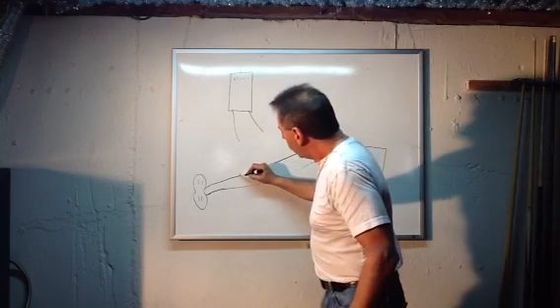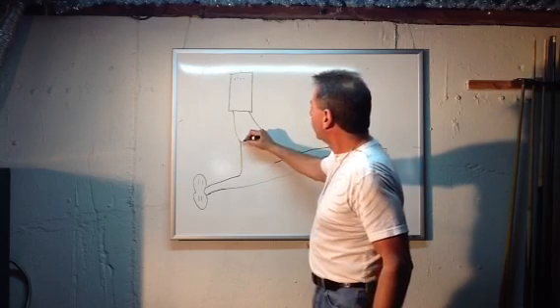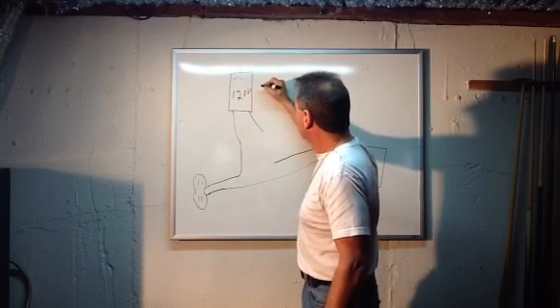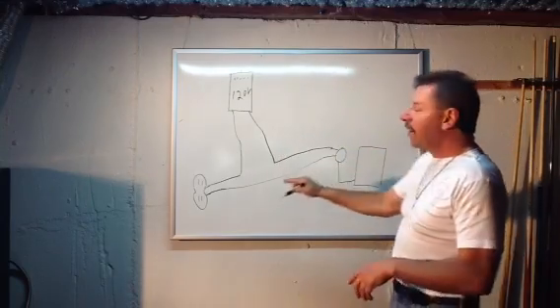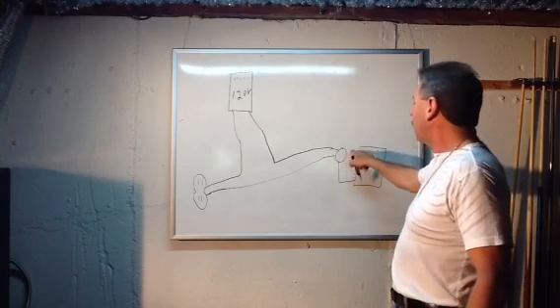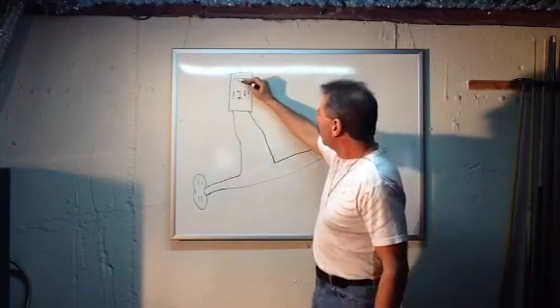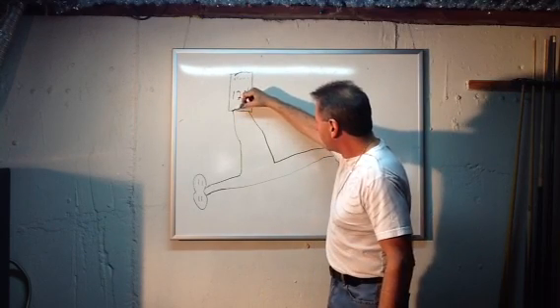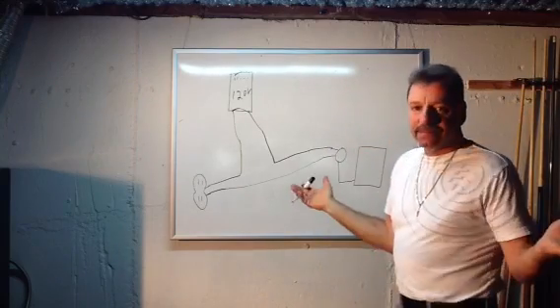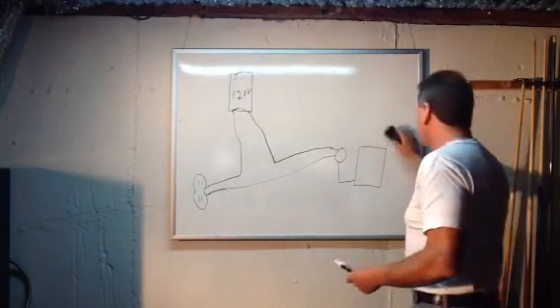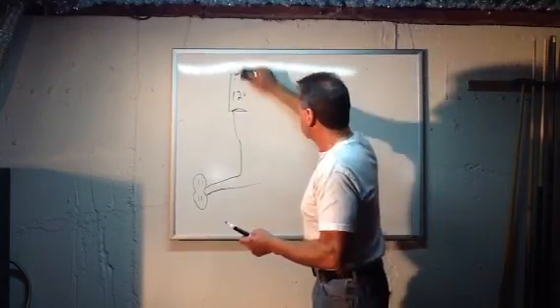Simply wire-nut it up to one wire of the line voltage thermostat—remember this is 120 volts—and the other wire back down to the other end of your cut. Now the power has been disrupted going into the circulator pump, and it cannot run until this thermostat says so. When you put the dial up, it simply joins these two wires together inside itself. That's it, your zone is wired—one line voltage thermostat, no controls. You can do it.